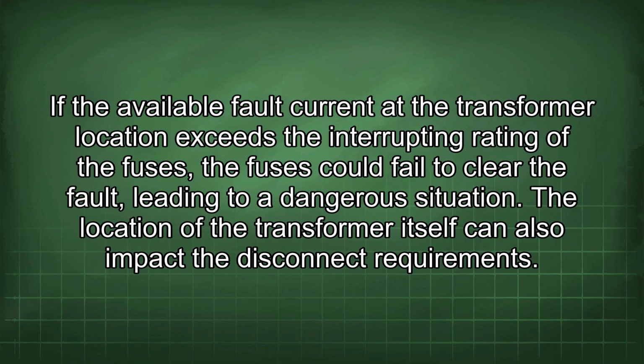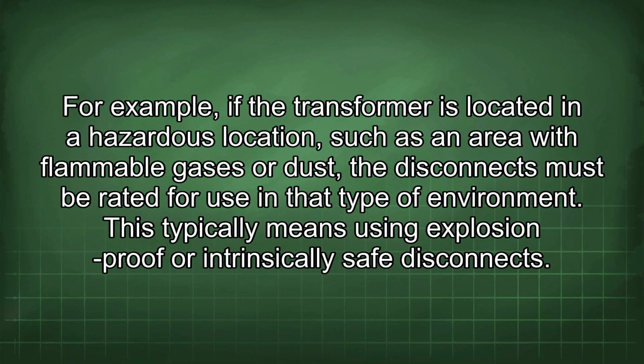If the available fault current at the transformer location exceeds the interrupting rating of the fuses, they could fail to clear the fault, leading to a dangerous situation. The location of the transformer itself can also impact the disconnect requirements. For example, if the transformer is located in a hazardous location, such as an area with flammable gases or dust, the disconnects must be rated for use in that type of environment. This typically means using explosion-proof or intrinsically safe disconnects.